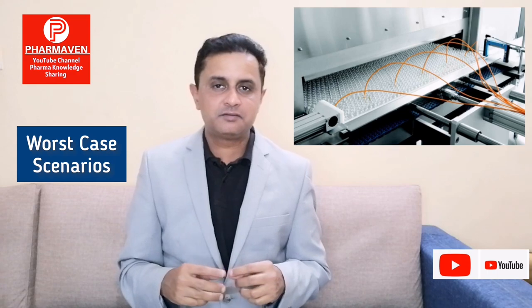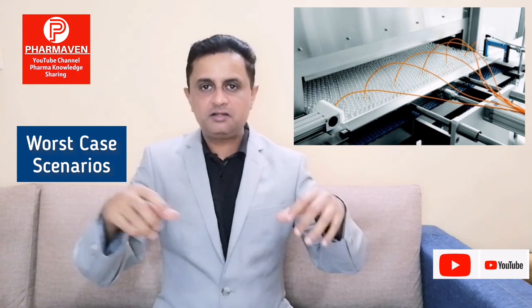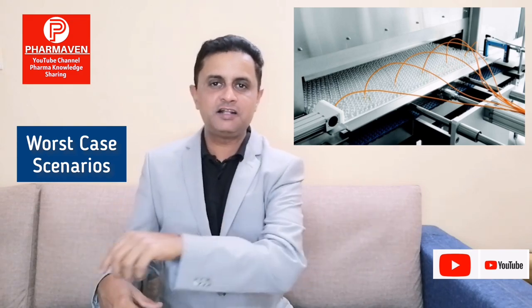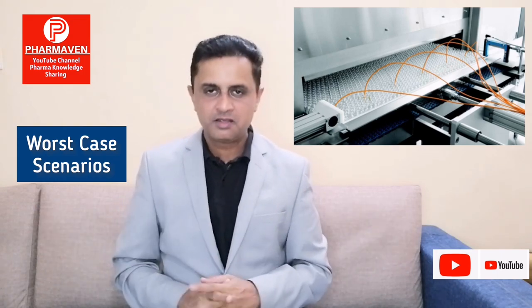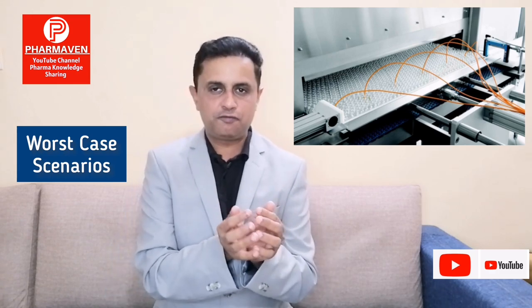And how can I measure? We have to carefully place the sensors throughout the width of the conveyor. If my conveyor width is 300 mm, then from this end to this end, maybe 5, maybe 10 sets of vials with sensors inside I have to put. And how can I put them? There are two ways. One is to keep a bunch of vials tied with Teflon tape and put the sensor inside. This bunch will not allow the sensor to move here and there, or the vial with the sensor to topple. The second way is to prepare a stainless steel jig with holes inside.